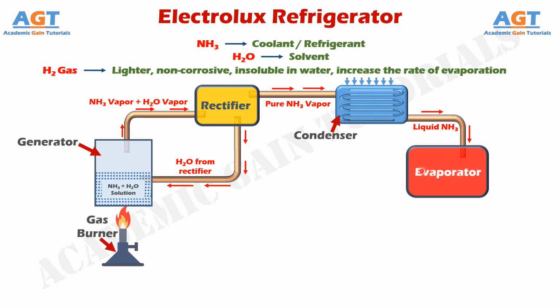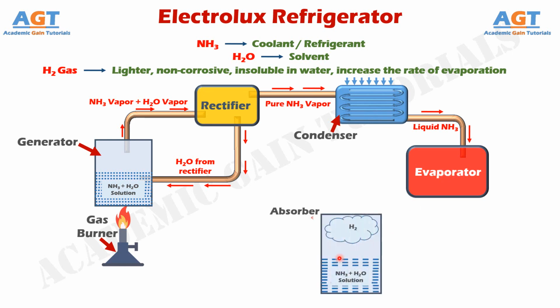But here inside this evaporator, one more fluid will enter the process, which is hydrogen gas. Now, from where are we getting this hydrogen gas? If we see, here we have an absorber. In the lower portion of this absorber we have water, and in the upper portion of the absorber we have hydrogen gas. As we already know, hydrogen gas is insoluble in water, and it is lighter in weight, so the hydrogen gas remains floating in the upper portion of the absorber above the layer of water. And since hydrogen gas is very light, it will go through this connecting pipe and enter the evaporator.